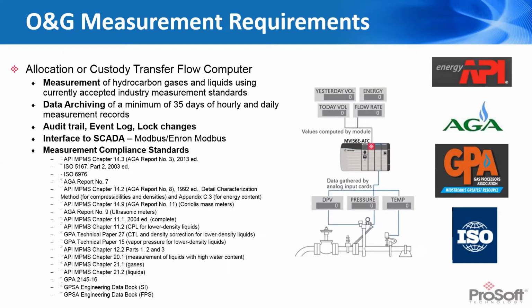The API minimum requirement is 35 days' worth of hourly and daily records. And then additionally, you have to have a secure audit trail, an event log, and then the ability to lock out changes or keep track of all these changes. So as something like an orifice plate or gas analysis data is changed for a measurement operation, that has to be stored into the event log of a device, and it has to be recorded at what date and time that information was changed.